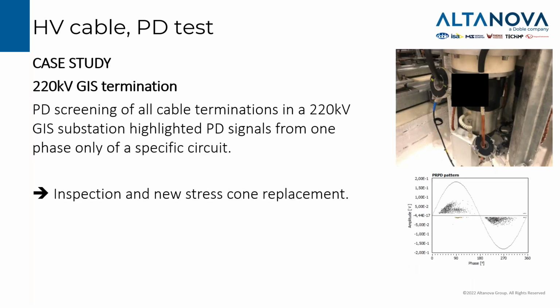Here we have a case study about GIS cable termination. The customer called us to perform a survey, so a PD screening of all the cable terminations of a 220 kV substation, and it was possible to find PD in the GIS termination. It was then inspected, and a new stress cone was placed instead of the defective one.